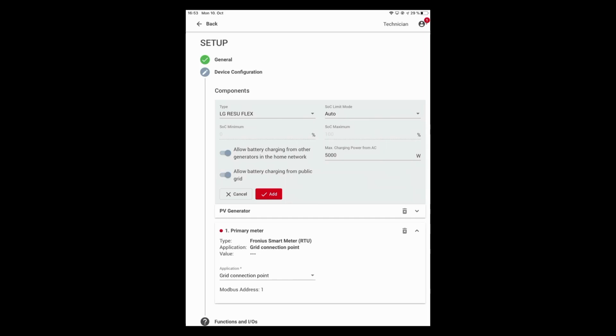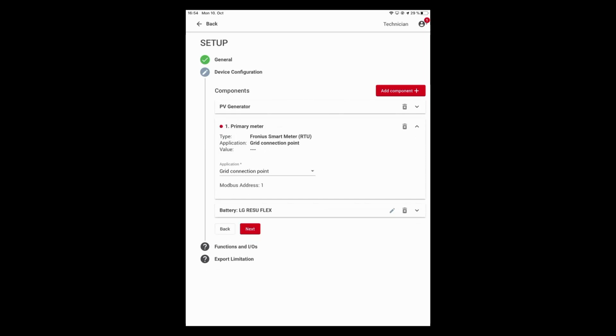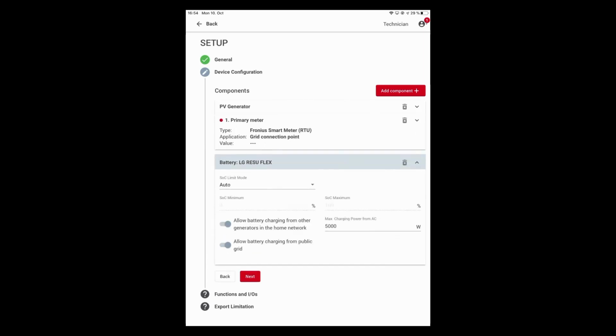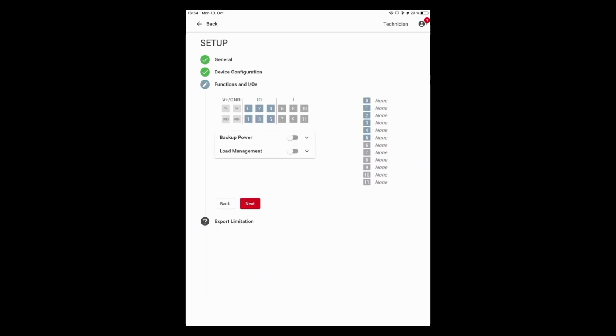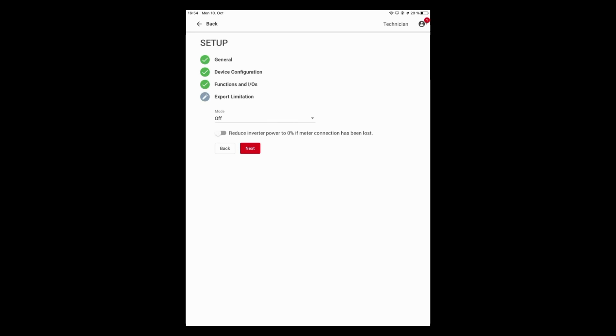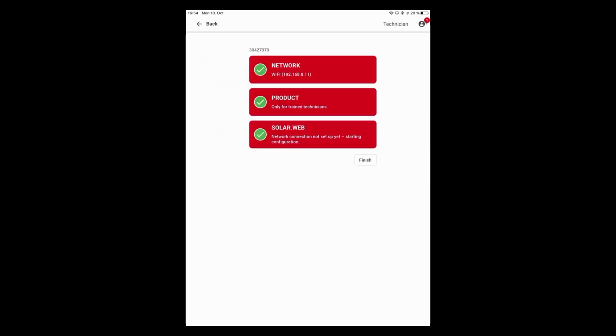Furthermore, you can also allow battery charging from the public grid, so this comes into play when you use our time of use functionality and want to charge or discharge the battery system at specific times. Yeah, then you just click on add, and then the LG battery system is already added to the system, and afterwards you can click on next to save these settings. Yeah, furthermore, you can also use functions and IOs for backup power or load management, and of course our export limitations. If you want to know more about these functionalities, please check out our other webinars and trainings on the first commissioning of the GEN24 Plus products.